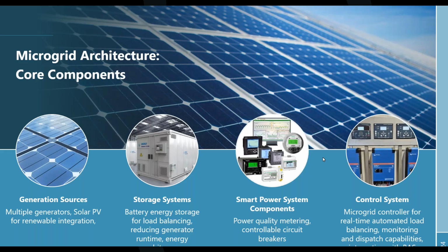Then we have our smart power system components: controllable circuit breakers, advanced protection and control devices, and finally our control system, the microgrid controller, which takes the place of the grid operator in your system by orchestrating which sources turn on and off as required, and which loads need to shed if needed. Load shed just means disconnecting them, turning them off if required, to maintain stability.